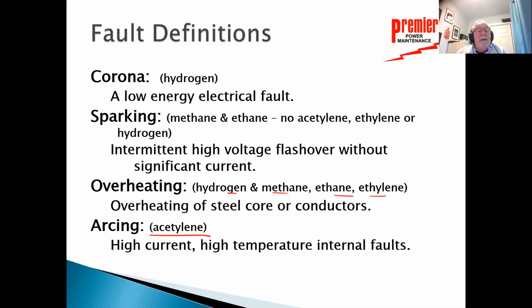Now, again, these items, corona, sparking, arcing, probably not a lot you can do about that. You may have to get inside the transformer, you may have to get the transformer repaired, but at least you've got an indication of what's going on. Overheating, if it's not just local overheating, you might be able to correct that with your operational procedures.